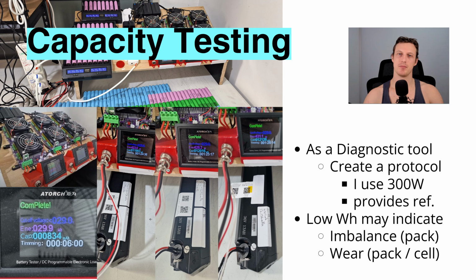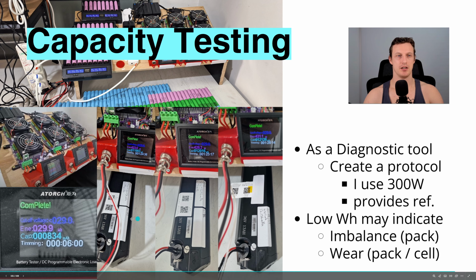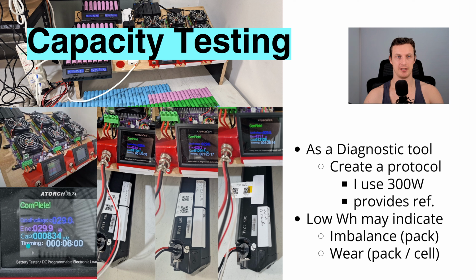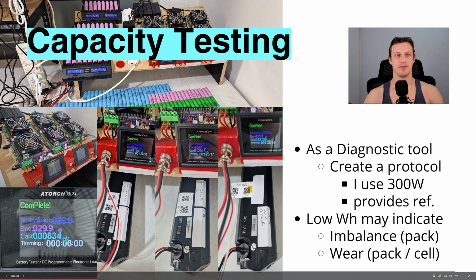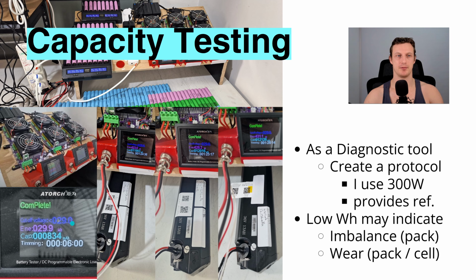Now, sometimes you can pick up anomalies through capacity testing. For instance, the photo in the bottom left-hand corner was of one of these packs, but it had a very badly imbalanced cell group. Therefore, it produced very little energy before the BMS cut off, resulting in only about 30 watt hours being measured, whereas the normal amount would be around about 430.